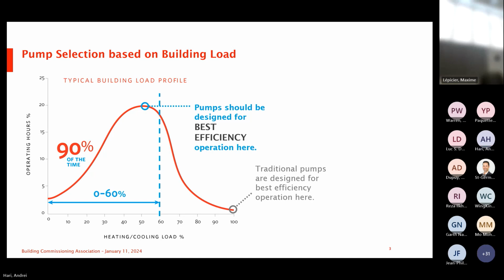So first of all, if we look at the industry as a whole on the HVAC side, historically we've always been operating in a constant speed, constant volume mentality, and we've been designing our pumps based on a design point efficiency at peak load. Whereas as we've gone through, we understand that almost 90% of the time our pumping equipment actually operates at part load. And so with that understanding, there has been a focus for the last 20 years plus of moving away from a constant speed, constant volume mentality to sizing your pumps based on part load operation and understanding maybe we should be looking at best efficiencies at part load, not at design.